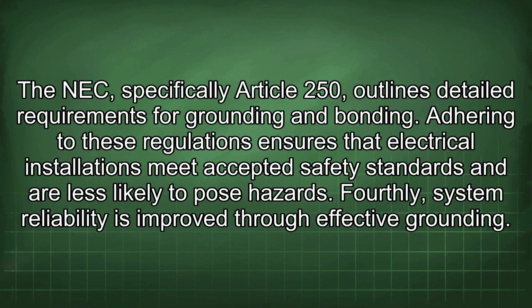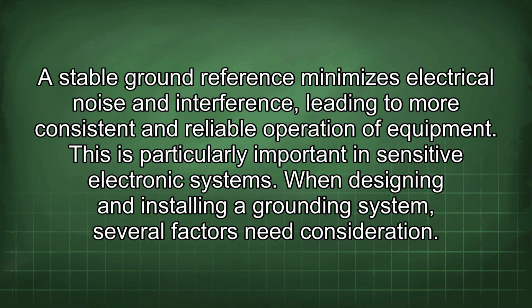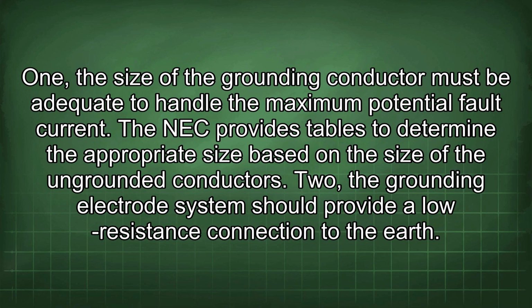Fourthly, system reliability is improved through effective grounding. A stable ground reference minimizes electrical noise and interference, leading to more consistent and reliable operation of equipment. This is particularly important in sensitive electronic systems. When designing and installing a grounding system, several factors need consideration. 1. The size of the grounding conductor must be adequate to handle the maximum potential fault current. The NEC provides tables to determine the appropriate size based on the size of the ungrounded conductors.